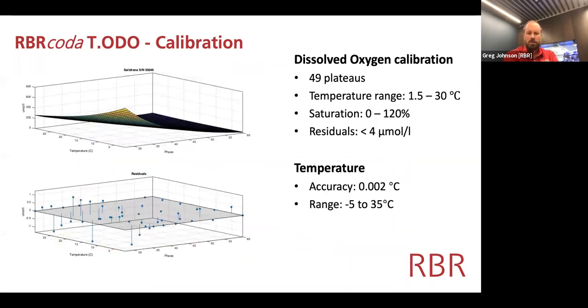How do we calibrate it? Well, I mentioned being able to do a 1 or 2 point calibration, and that's quite true when you're in the field. But in the factory, we do a much more complete calibration. We calibrate over 49 points. And those points are distributed 7 in temperature and 7 in oxygen. The response of the foil is very dependent on temperature. So we calibrate from 1.5 to about 30 degrees and 0 to 120% in saturation. And then we fit a polynomial surface to that.